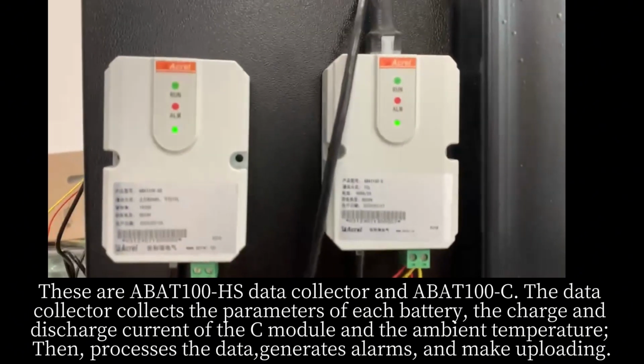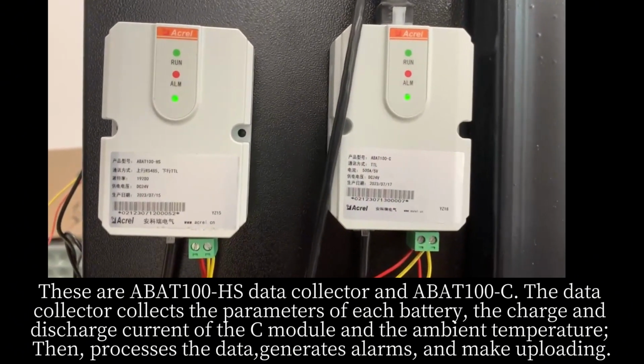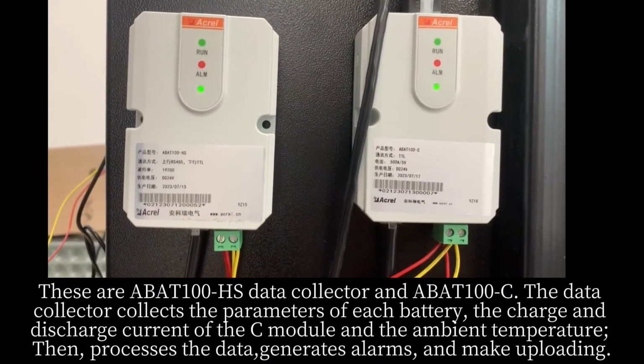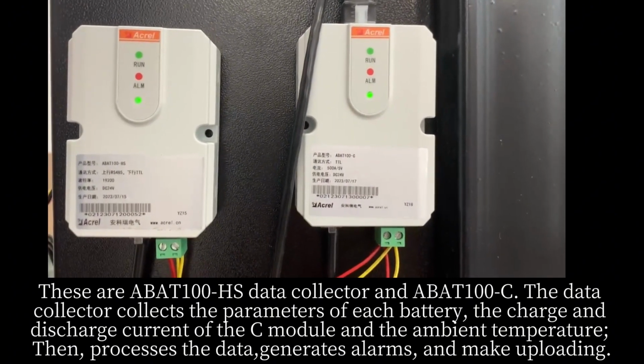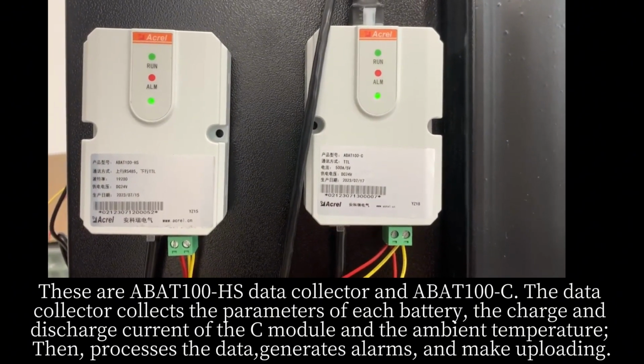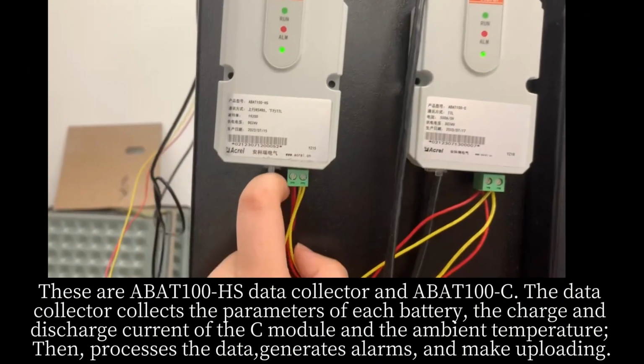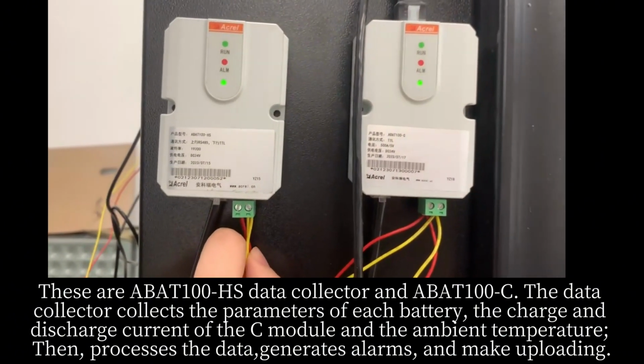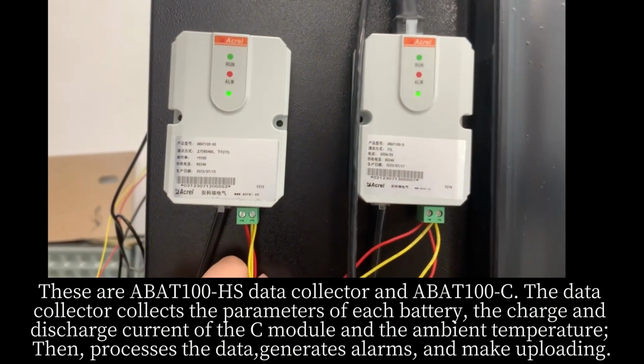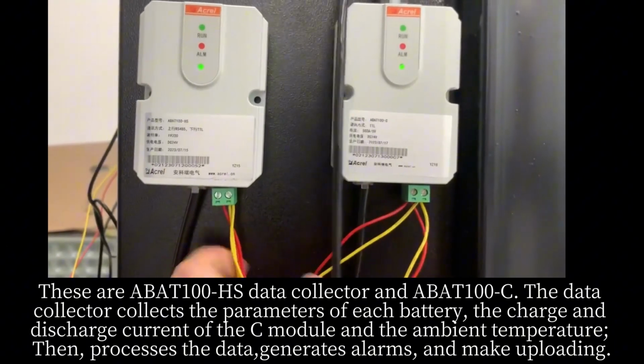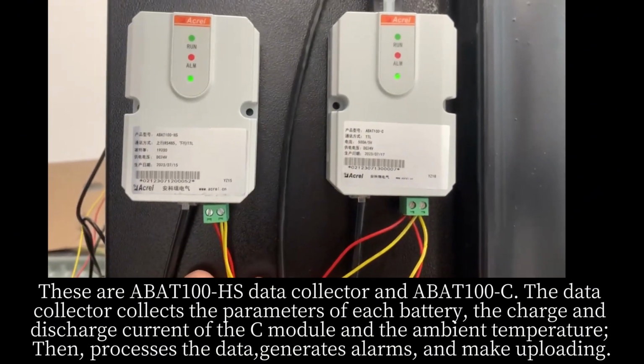These are the ABAT100-HS data collector and the ABAT100C. The data collector collects the parameters of each battery, the charge and discharge current from the C module, and the ambient temperature, then processes the data, generates the alarms, and uploads it.